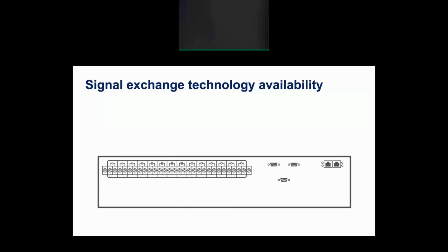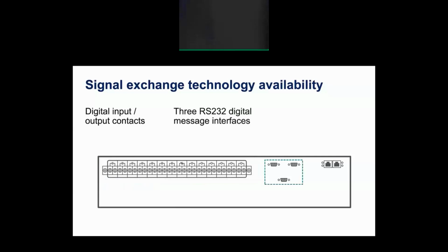We need to understand the quality of the different methods to exchange protection signals. So for hardwired I/O, we need to understand and preserve the operation of the physical contacts. So we need to understand shock and vibration, humidity, temperature, thermal expansion, all the things that cause wear and stress and corrosion on the contacts and affect the reliability. For serial communications and Ethernet digital message interfaces, we have to worry about connectors, microcontrollers, transceivers, and oscillators.